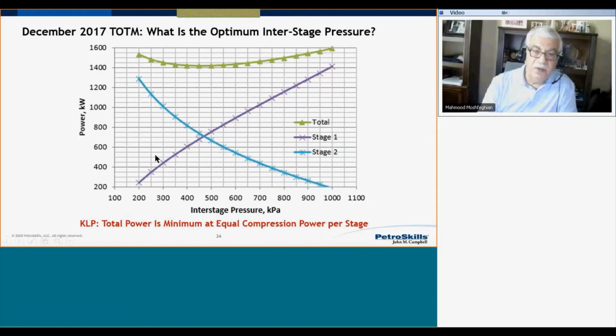To make my case, similar diagram, power requirement for stage 1, for stage 2, and total power requirement. At this point, the power for each stage is the same. And if I continue here going to the total power requirement, my total power requirement is minimum. So this verifies that the total power requirement is minimum if the compression power for each stage are the same. But when we teach in classes, we say we can minimize power requirement if you go equal compression ratio. So why is that not the case in this diagram here for our refrigeration system?